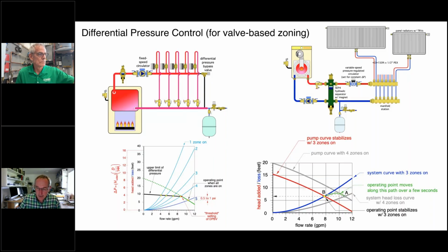Initially, the operating point is going to try to climb from A up to this point here. But the internal electronics in a variable speed pressure regulated circulator are going to sense that deviation from a constant differential pressure setting. In other words, they're going to feel the increase in differential pressure, and they're going to compensate by reducing motor speed. And when that happens, you can see this operating point eventually, within a few seconds, will settle down right here at point B. So the net effect is we've moved from A to B.